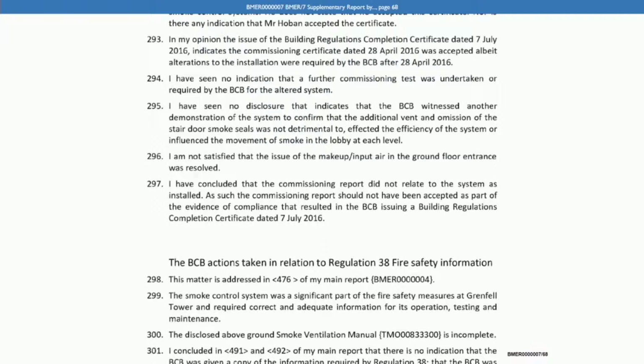This relates to, as you've identified, the suggestion by Mr. Hoban that an additional vent be added after the commissioning had been undertaken, yes, and then no additional commissioning process was carried out.